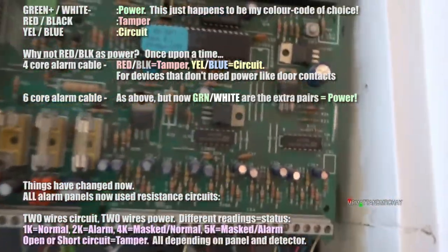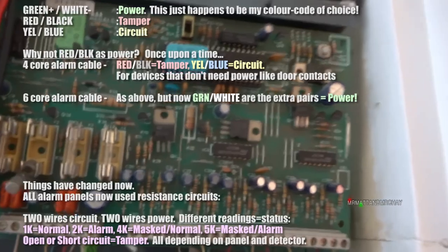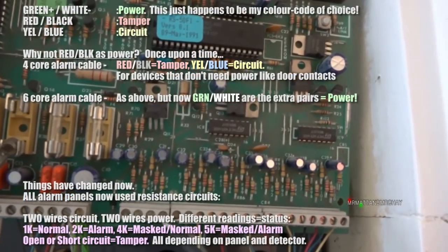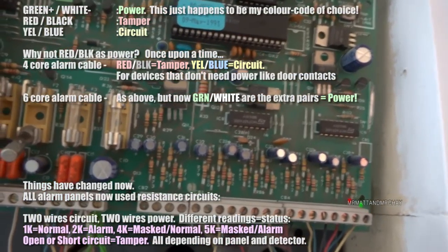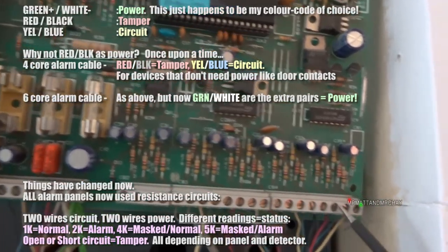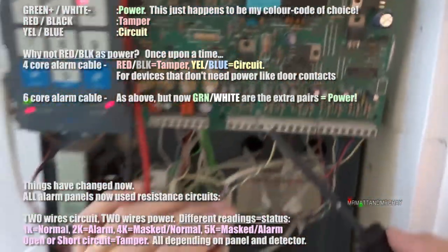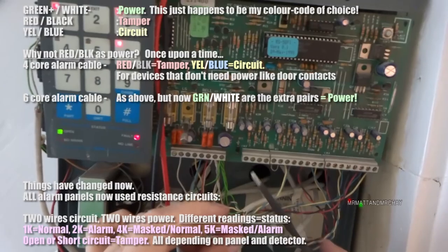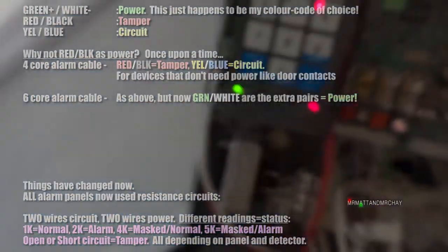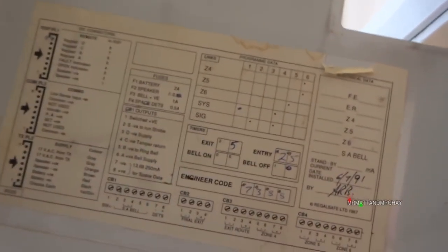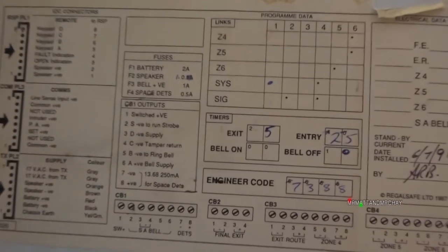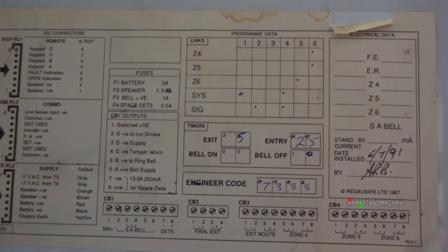So the strange thing about this panel is it goes tamper, circuit. So that's zone one, zone two, etc., down to the bottom here. Normally you have circuit first, then tamper. But the way I found this out is, it's on the lid. Shows you what's what. There we go.